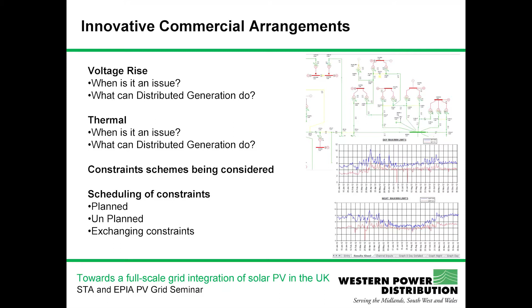Innovative commercial arrangements. The network is designed pessimistically as a passive fit and forget connection, which means we calculate maximum generation, all the generation on the network, all at maximum at the same time. It's credible, it can happen. At the same time, we have minimum demand.